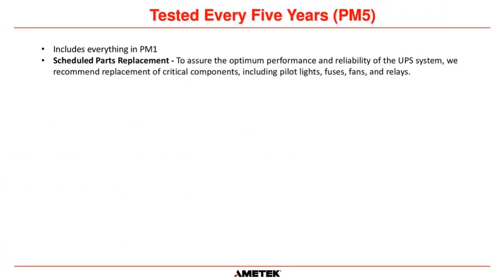Then we have the PM5. So every 5 years, we do everything that's included in the PM1. And then we also recommend that you replace the pilot lights, the fuses, the fans, and the relays. Okay, so it's mainly the fans that are the most important thing during the PM5 because of the design life of the fans from the manufacturer.